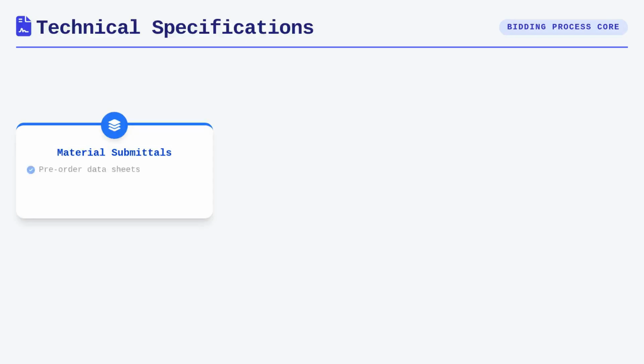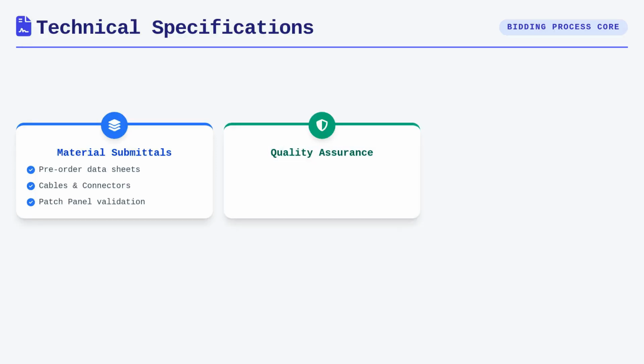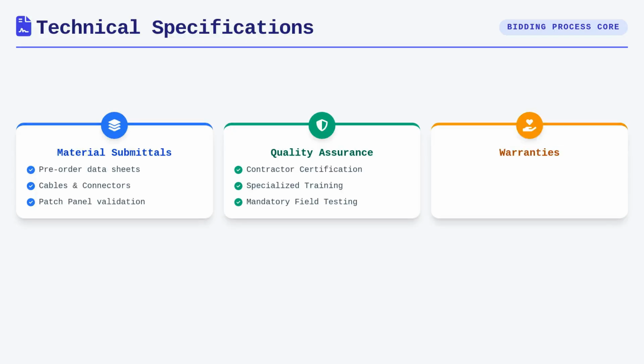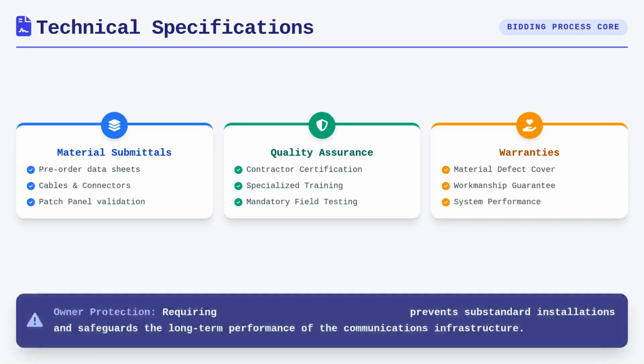Technical specifications form the core of the bidding process and demand precise language concerning materials, methods, and quality. You must clearly outline the material submittal requirements, such as requiring data sheets for every cable, connector, and patch panel before ordering occurs. Quality assurance mandates are equally vital, as they define the standards for contractor certification, specialized training, and required field testing. You should also explicitly state warranty conditions, defining the specific requirements for system warranties against defects in both materials and workmanship. When you demand proof of manufacturer training for technicians, you are directly protecting the owner from substandard installations that would otherwise jeopardize the long-term performance of the communications infrastructure.